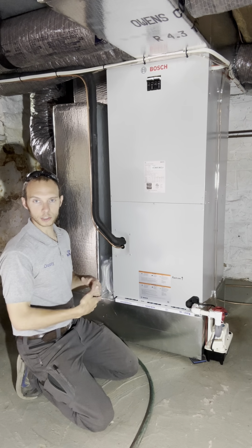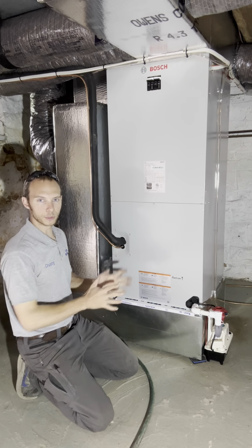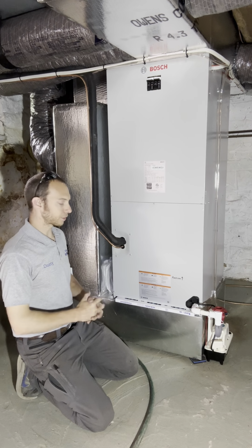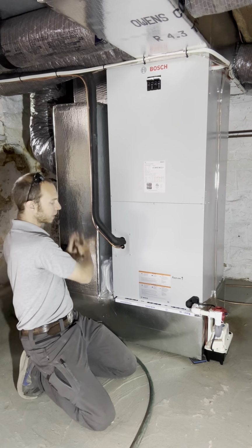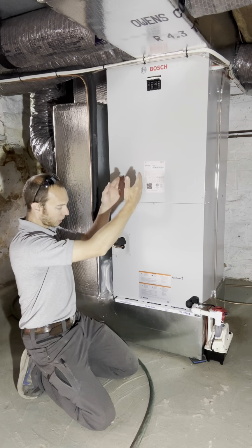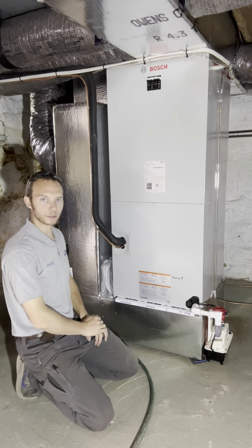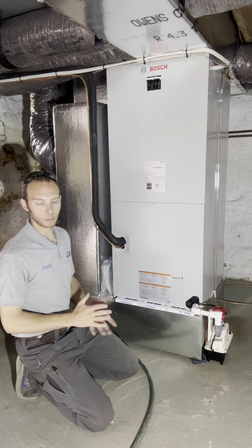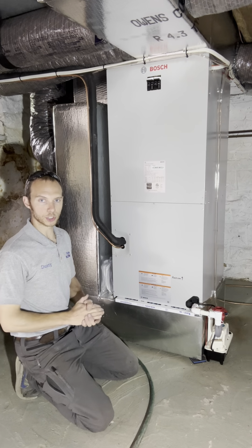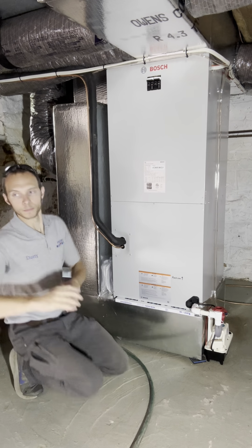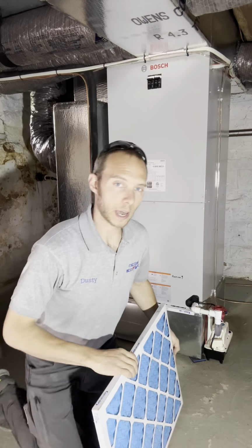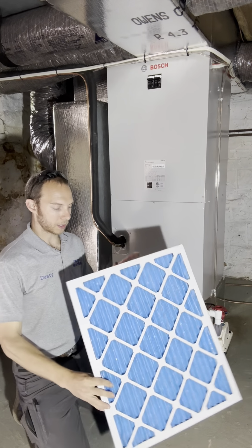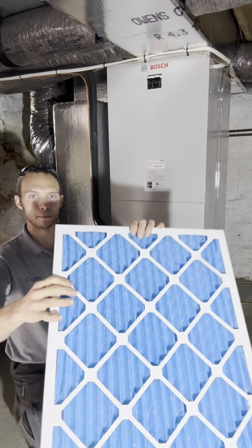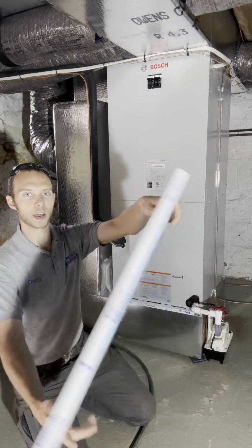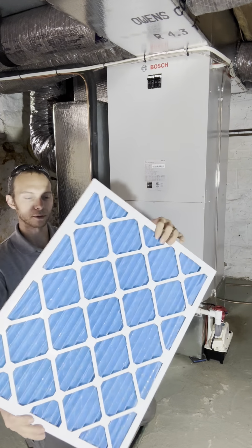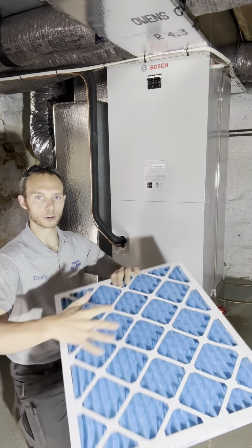There are inverted units out there. I'm not sure why people would install that in a basement, but they are out there. This particular application, we're bringing the air in this side and coming up through this way. So you have to be aware of that for the sake of your air filter. For the most part, it's not a big deal as long as you're changing them on a regular basis. The reason that that would be important would be because the air filters have a metal mesh on one side and not so much on the other. This particular one has a lot of cardboard crosses.